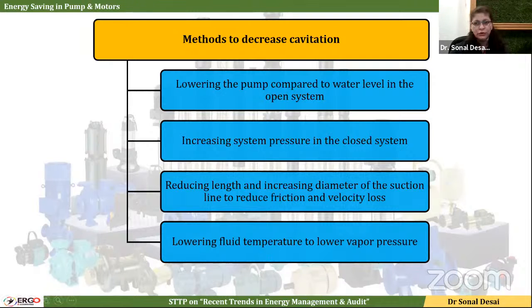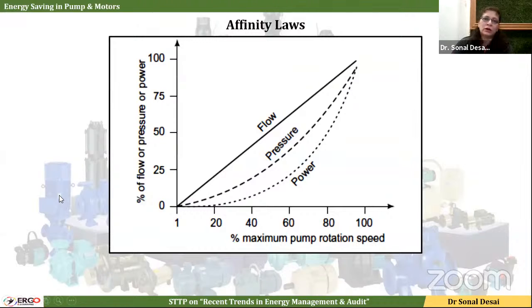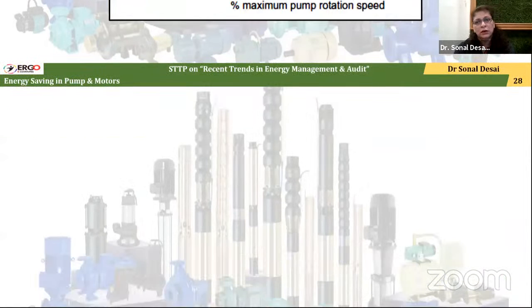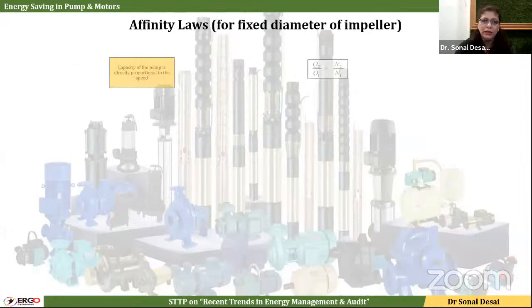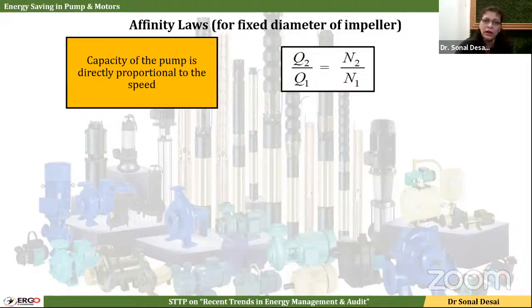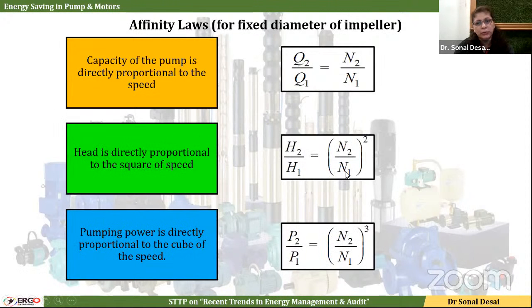Lowering fluid temperature, because if we are handling high temperature fluid or viscous fluid, then again, this is going to occur in the pump. So coming back to the affinity laws, they are basically for either a fixed diameter or a fixed speed. So the affinity law, when we talk about a pump, says flow is related to speed in a direct way. When we talk of head, it is proportional to the speed squared. And when we talk of power consumption, it is in proportion to the speed cubed.